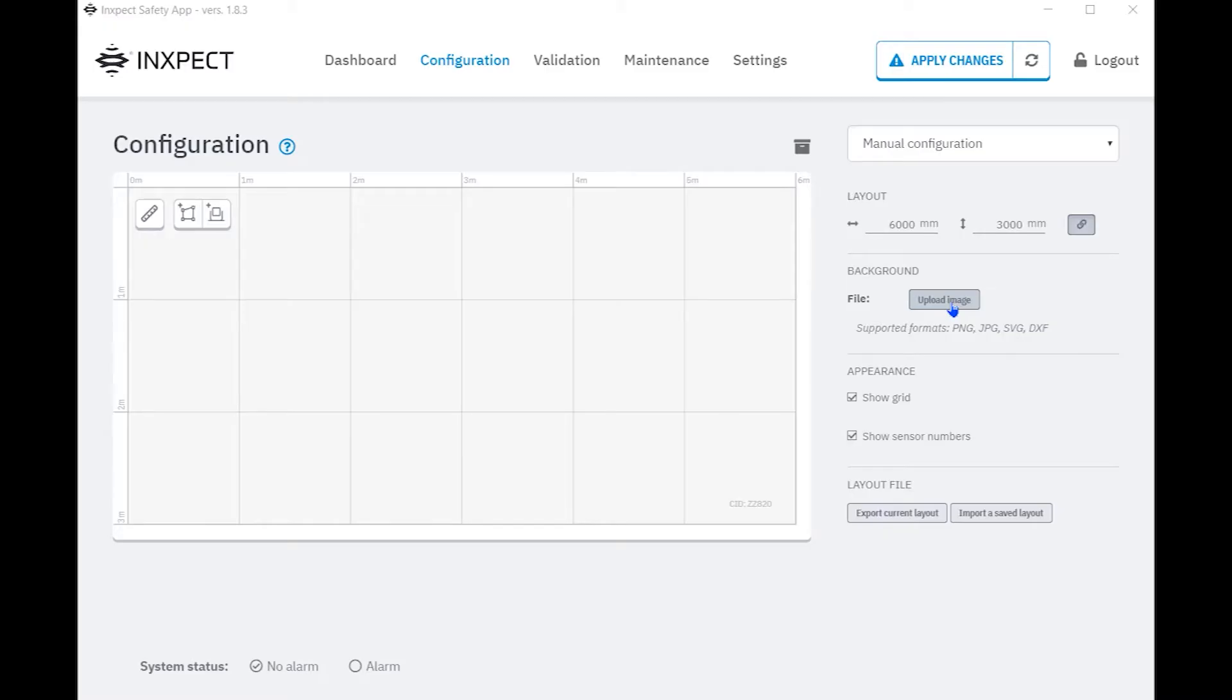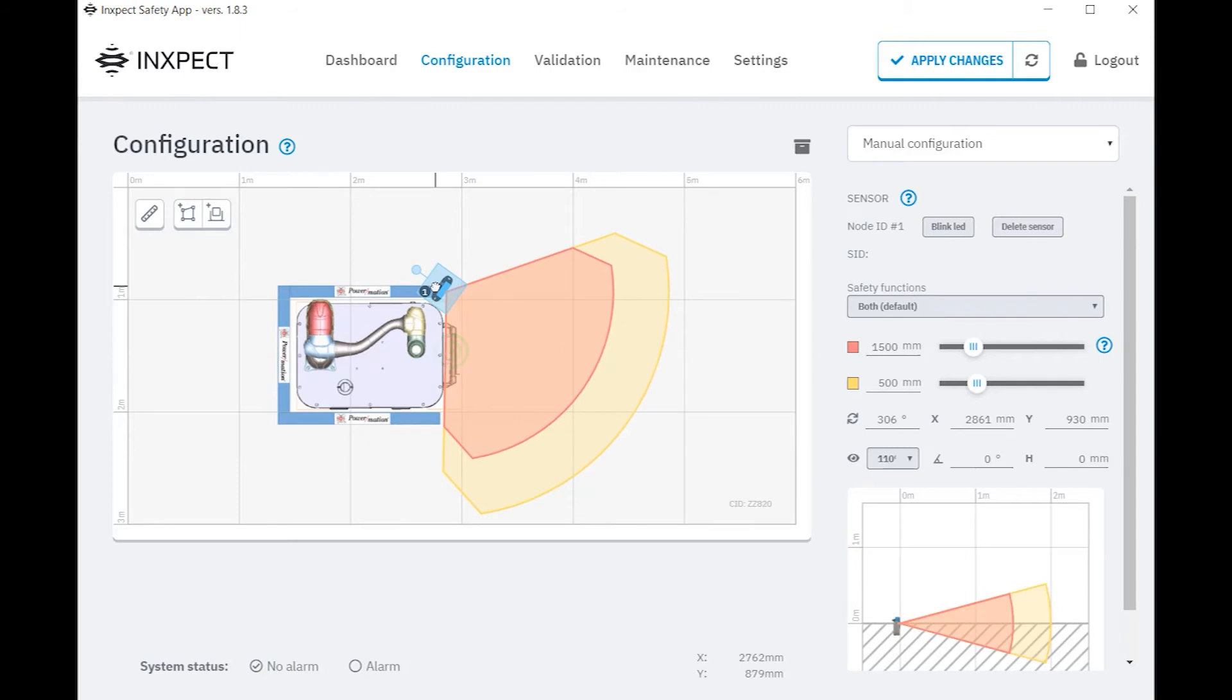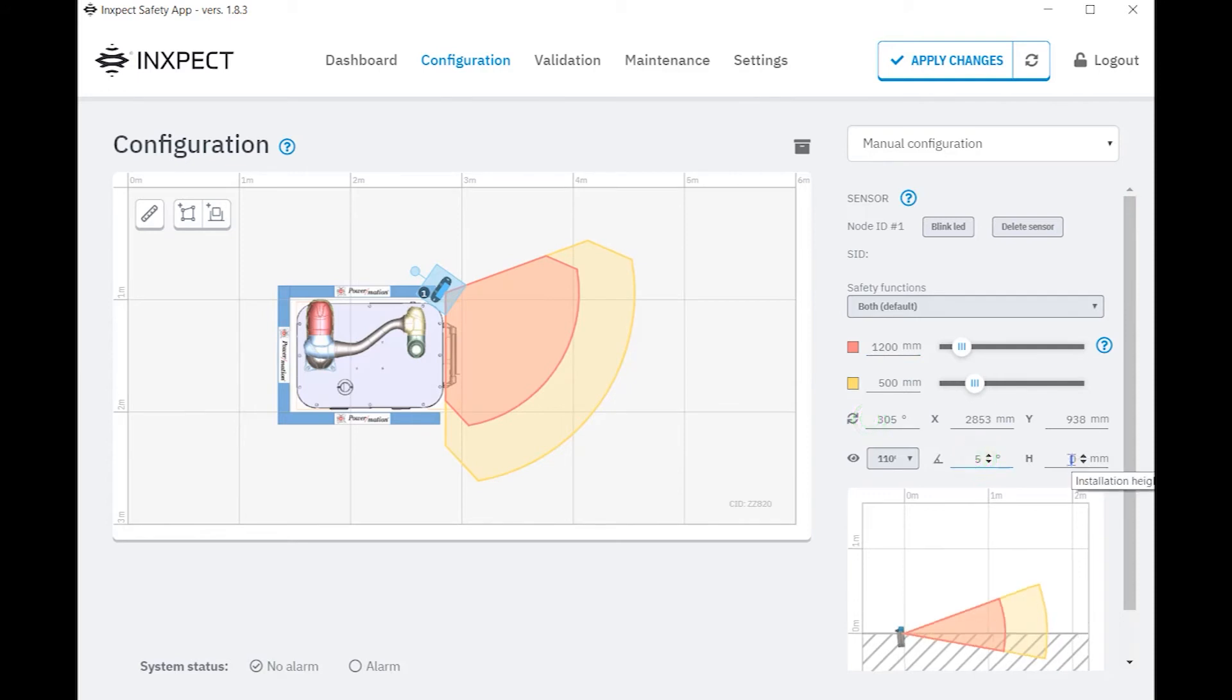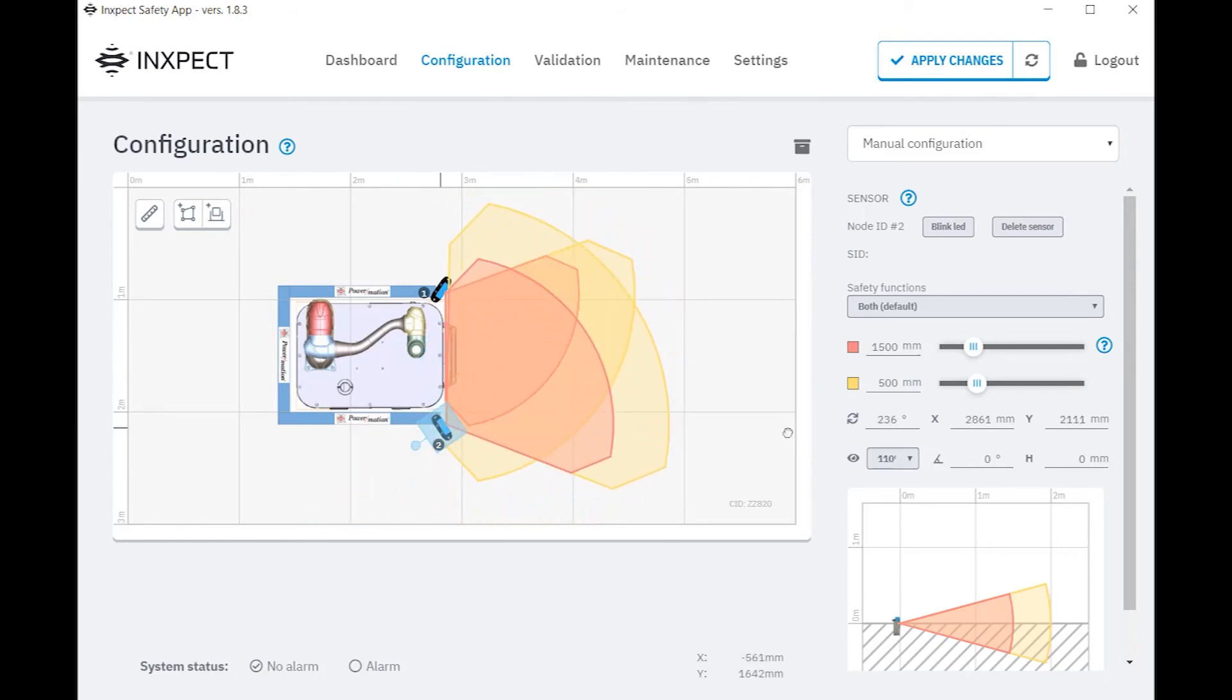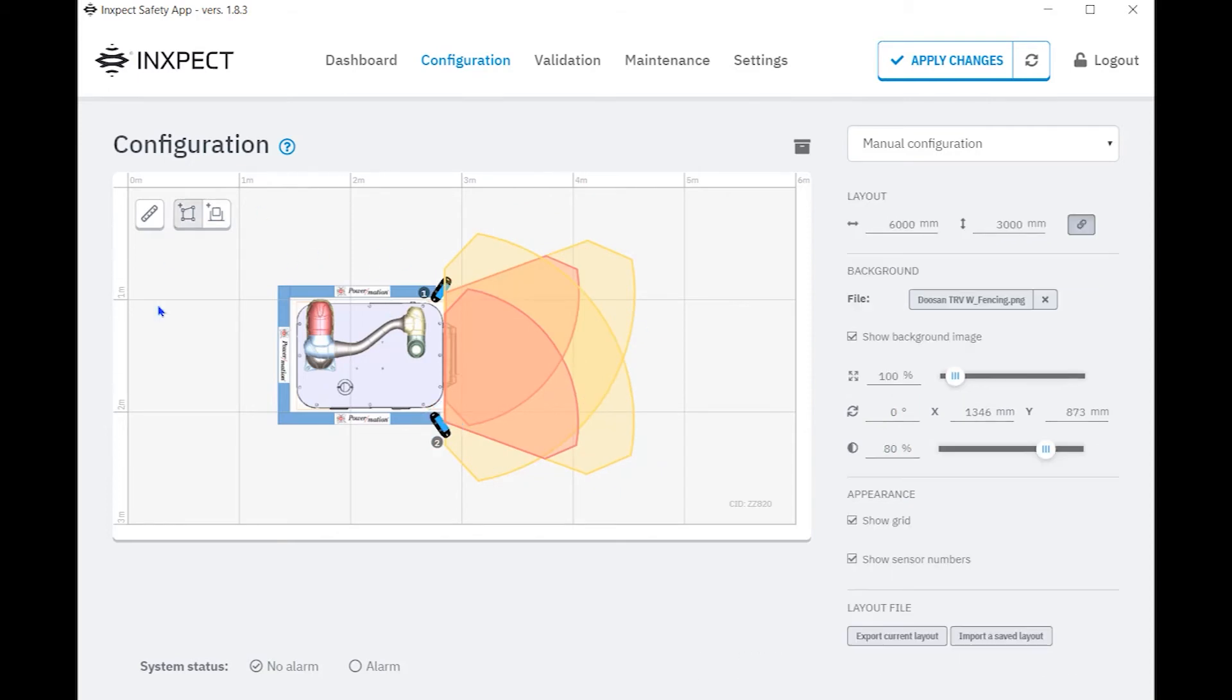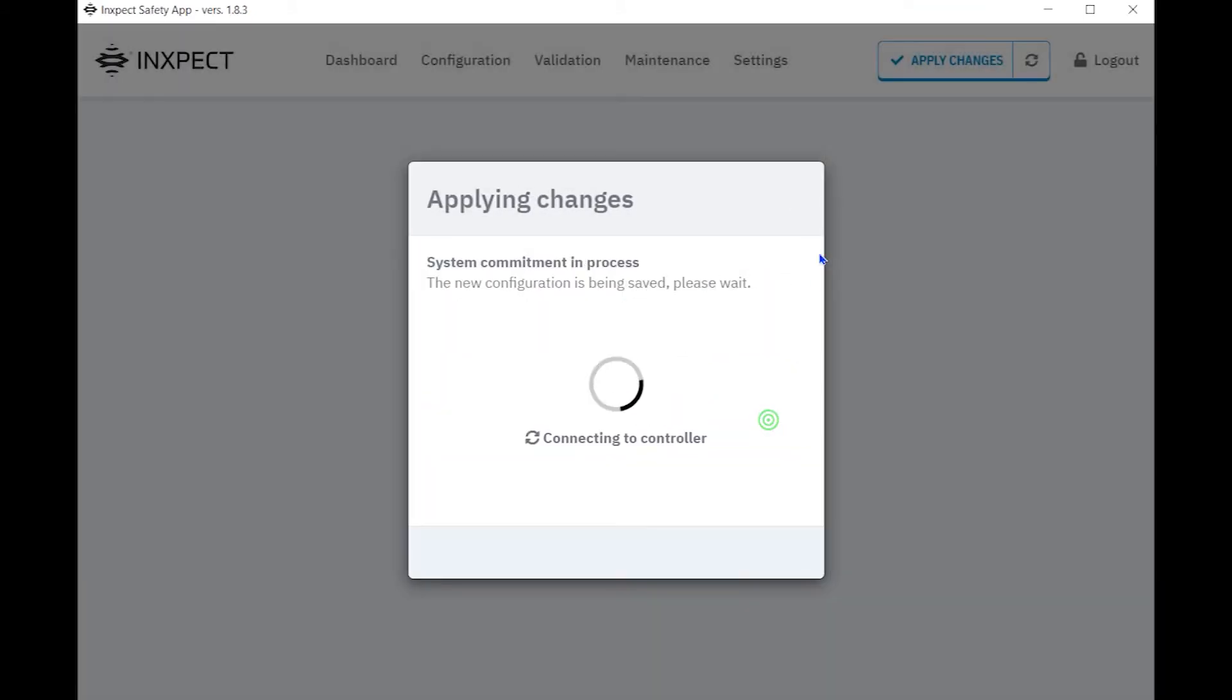In the configuration page of the InXpect software, we're going to upload the image file, position, and properly scale as required. Select add sensor and position as needed. Adjust field of view settings for the appropriate coverage of the stop and warning zone. For sensor number two, we're going to click the add sensor button and replicate the process. Once the appropriate settings have been entered, the sensor's field of view configurations are now complete. We are now ready to transfer these settings to the controller and can be done by clicking the apply changes.